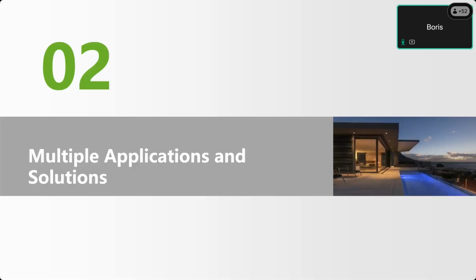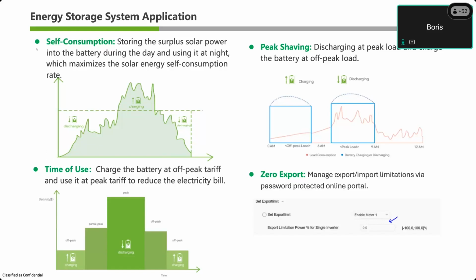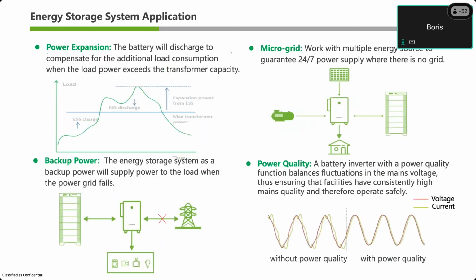Multiple applications and solutions. I'd like to show this really quick just to show that our inverter, again, we're trying to make this a one-stop shop for all commercial applications. We have self-consumption modes, peak shaving, time of use, zero export. I have some more on the next slide, but these are all programmable via our own internal software. You can do this through our portal remotely, so you can adjust that as you need. It can be password protected. You can do it locally over our app, Shine Server app. So these settings are all programmable, and then also you could do it over Modbus. Let me just show the next slide to show a few more. Power expansion, microgrid, backup power and power quality adjustments can all be done through the inverter.